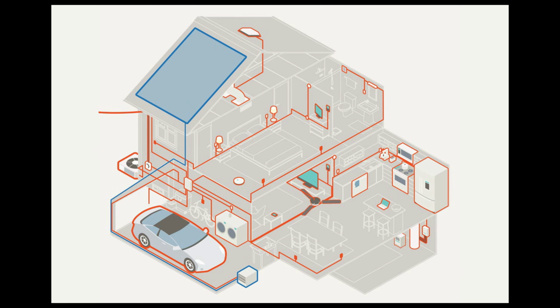As I've seen in my test with the Regenerator, using a power quality analyzer, these RFI and EMI noises seem to be at a much higher frequency than 3000 hertz, as they didn't show up as a harmonic on the main power coming out of your outlet. Also think about solar power. Solar power uses an inverter and is connected to the utility. If you don't have solar power, your neighbor's solar power roof, a house or 2 away, could be injecting harmonics as well as EMI noise on the electric line coming into your house as well as your neighbor's houses.